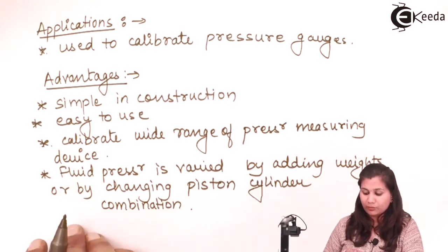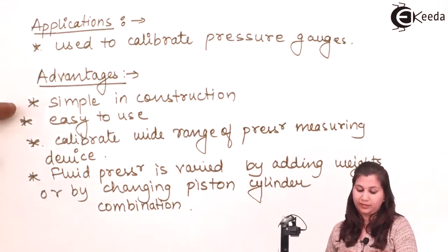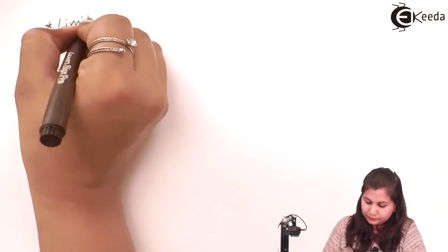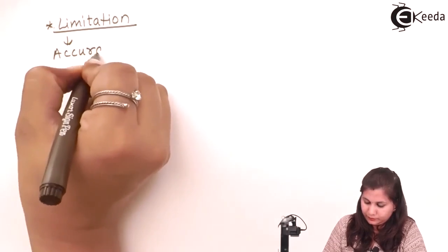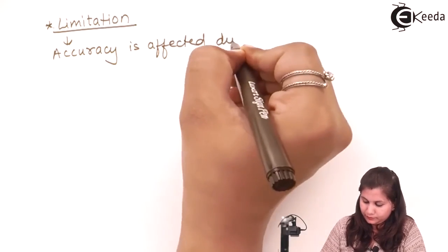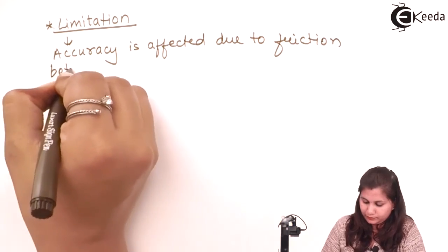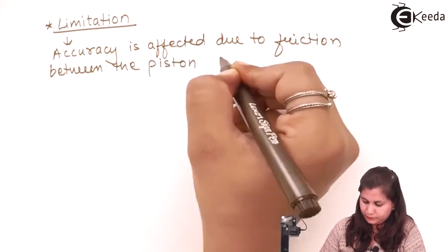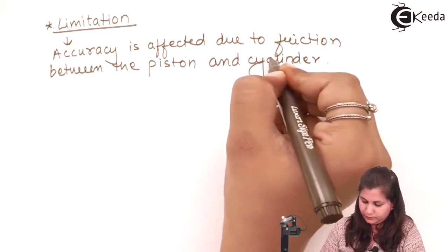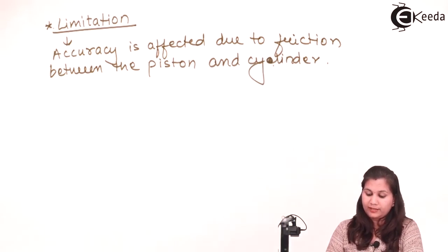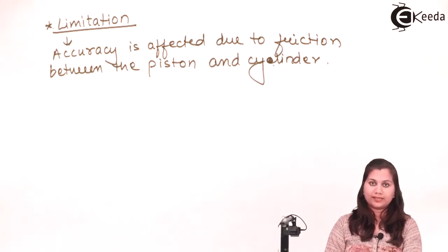If we talk about the disadvantage or the limitation of the deadweight tester, its disadvantage is that as the piston cylinder is a combination, it is moving, so due to the moving parts in the apparatus there is friction, and due to that friction the accuracy of the instrument is reduced. Okay, so these are the limitations of the deadweight tester.